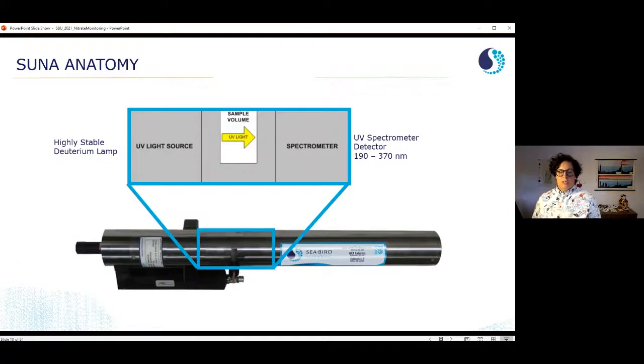Okay. So what does the SUNA look like inside? I talked a little bit about it, so really the basics of what the actual sensor looks like. This is based on technology that was developed at MBARI. If you look at the SUNA, there's a little notch in it, and that's actually where the sensing goes. That's the sample volume in there. On the left, you'll see that we have a UV light source. That's a stable deuterium lamp that provides a range of light in the wavelengths of the UV spectrum that goes through the seawater, and then you're going to actually measure that with the spectrometer. It measures the wavelengths that are shown there.